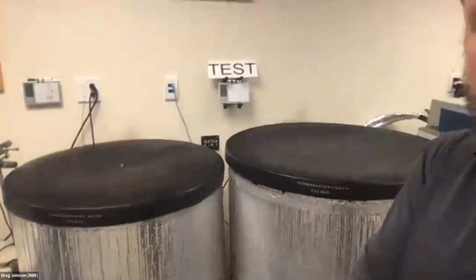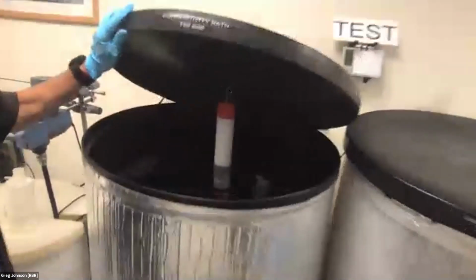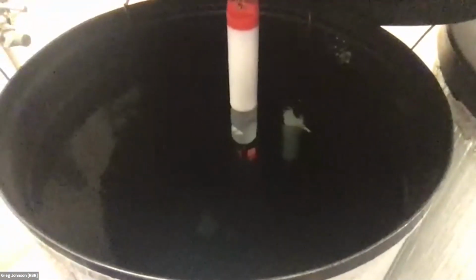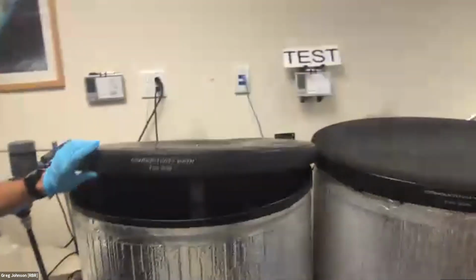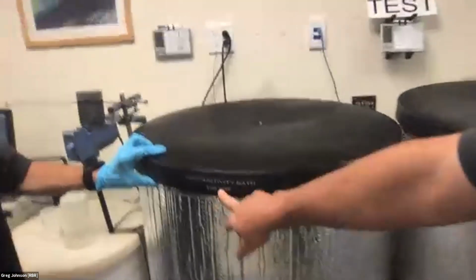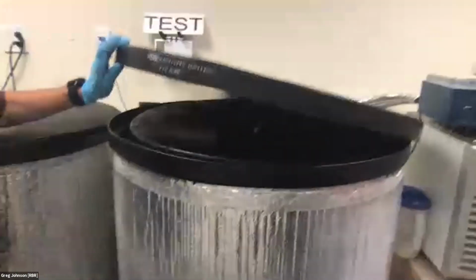Let me wander around and show you some of the calibration tanks that are here. I'll talk more details about the calibration process later. Igor, would you mind just giving me a hand lifting the lid on one of these? So we have two tanks here, which are both about 700 liters. This is an instrument that's undergoing calibration at the moment. It's just a well-stirred bath with some slight insulation around it, and typically at about 25 degrees. So this is T25S35. And then this tank is much better insulated. It's running at 15 degrees, so it's actually a tank within a tank with a cooling jacket, and we've got a couple of instruments there.